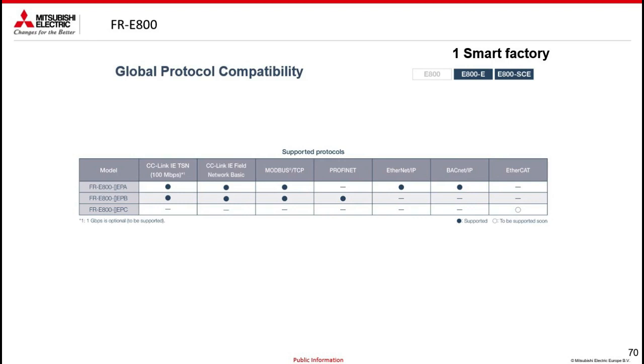For example, if you go to get the FRE800 EPA model, you already have on board multi-protocol, such as the CC-Link IE TSN, which is our new field bus, the CC-Link IE Field Basic, the Modbus TCP/IP, the Ethernet IP, and the BACnet IP. So already with this model you can choose between one of these protocols rather than going to get the EPB model. You already have the CC-Link IE TSN, the CC-Link IE Basic, the Modbus TCP/IP, and the Profinet, or the EPC that has the EtherCAT.